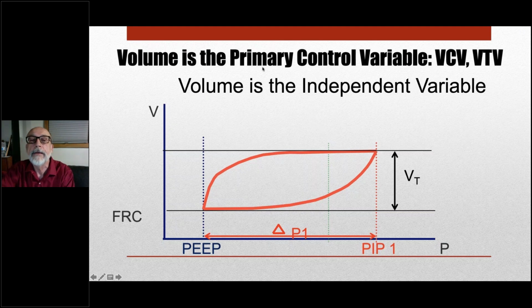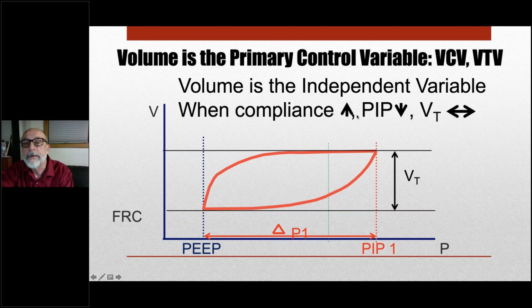So if we look at volume as the primary control variable, and this is typically how adults and pediatric patients are ventilated, volume is the independent variable. Volume is what you set. And this is a classic pressure volume loop, pressure on the horizontal axis, volume here. And so what happens when compliance increases? So here's the loop with the lungs that are quite stiff, so relatively low tidal volume and a lot of pressure. When compliance increases, it'll simply take less pressure to deliver that same tidal volume, because volume is what is fixed. Okay, so pressure goes down, tidal volume stays the same.